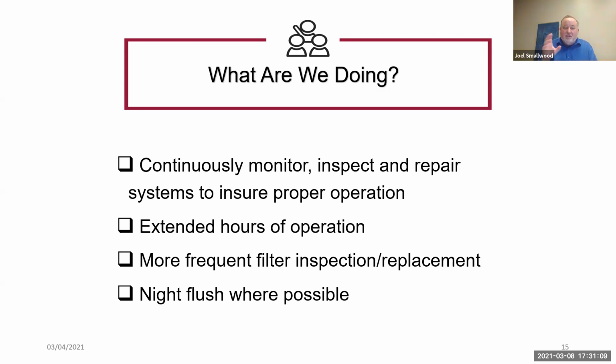The other thing is we can't get the rooms too terribly cold at night, because if we do a night flush and cool a room all the way down into the low 50s and then turn on that system at 6 in the morning, it won't be warm when everybody gets here. It'll take way too long for that building to recover. So as our nights start to warm up, as we move into spring, we'll be able to do more night flushing for longer periods of time. For right now, we have to keep that fairly minimalistic in order to keep the buildings warm.